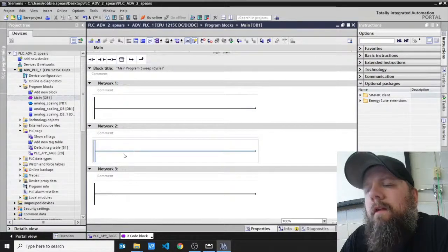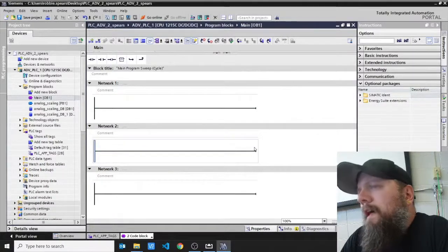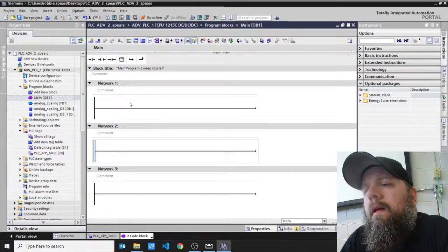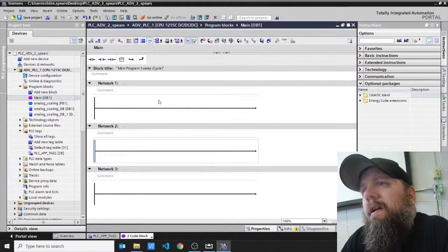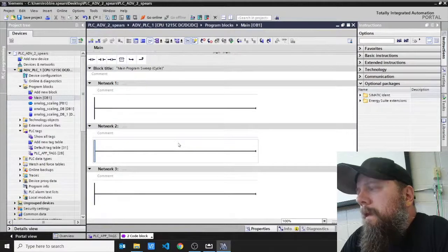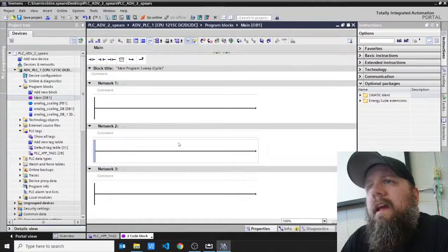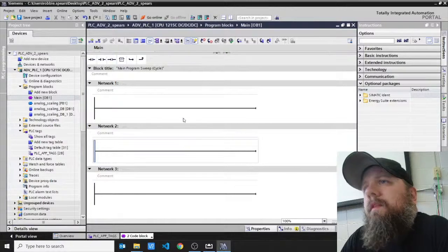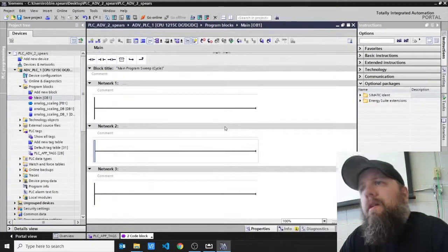When you've got a lot of networks, the way they process is fairly lateral or parallel. These are going in such a quick round robin that you could think of them as happening at the same time, right? If you have some logic going on there, some logic going on there, and some logic going on there, when it does that read cycle, it's like everything happens at once, right? There's very little one-after-another processing, okay?